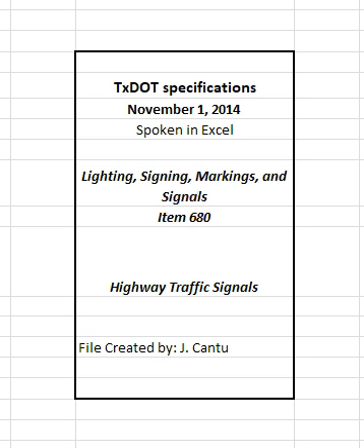3.1.2 Controller assemblies. Construct controller foundations in accordance with Item 656, Foundations for Traffic Control Devices. Immediately before mounting the controller assembly on the foundation, apply a bead of silicone caulk to seal the cabinet base. Seal any space between conduit entering the controller and the foundation with silicone caulk.